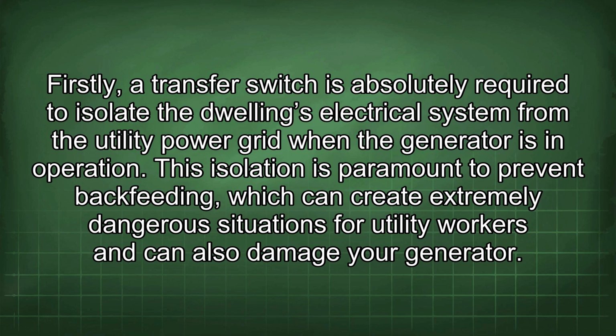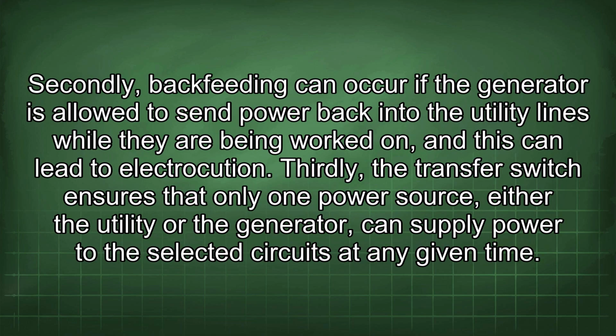Firstly, a transfer switch is absolutely required to isolate the dwelling's electrical system from the utility power grid when the generator is in operation. This isolation is paramount to prevent backfeeding, which can create extremely dangerous situations for utility workers and can also damage your generator. Secondly, backfeeding can occur if the generator is allowed to send power back into the utility lines while they're being worked on, and this can lead to electrocution. Thirdly, the transfer switch ensures that only one power source, either the utility or the generator, can supply power to the selected circuits at any given time.